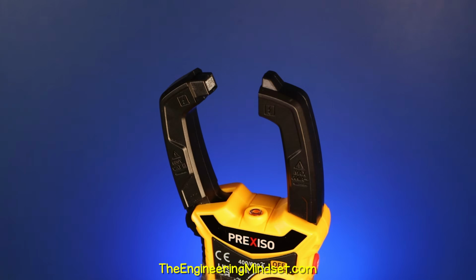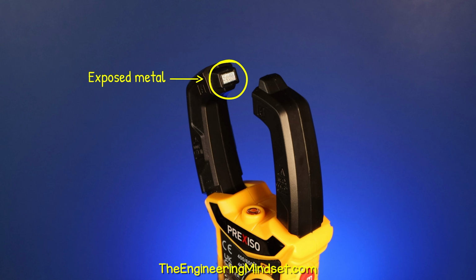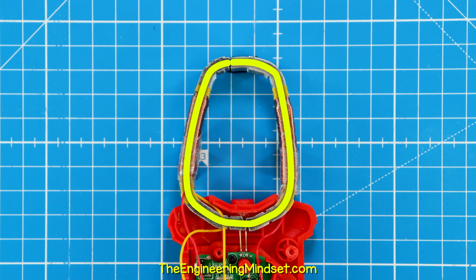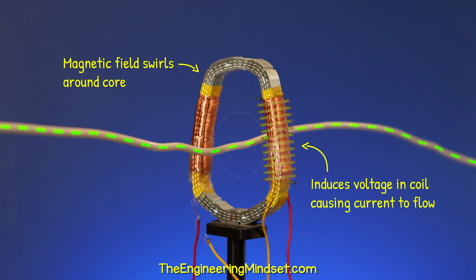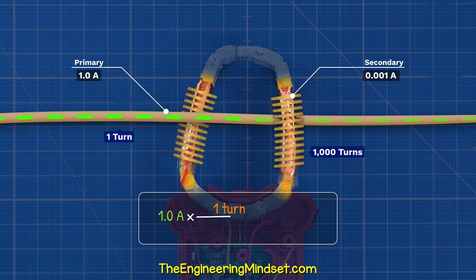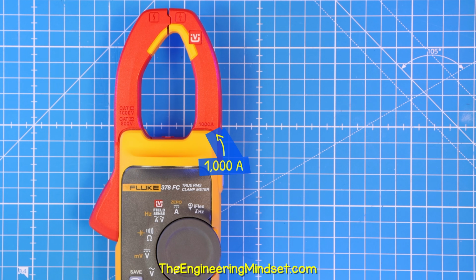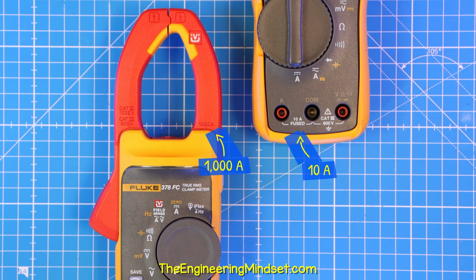That's why these meters have exposed metal surfaces inside the jaw tips to complete the circuit. The magnetic field induces a voltage into the coil, causing a small current to flow. That's because this is basically a transformer, so the current is very small and measured by the circuitry. That's why we can measure much larger currents than a standard multimeter.